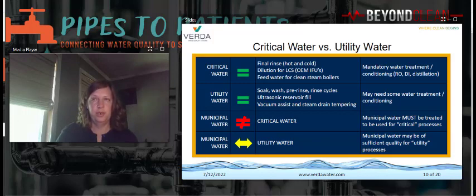Critical water must be treated and conditioned. Municipal supplied tap water isn't of sufficient quality for final washer disinfecting rinses or for pure dry steam for sterilizers. Utility water quality standards aren't as strict. Processes like basic soaking, washing, and rinse cycles use utility water. Also, utility water is used in the fill tanks in ultrasonic cleaners. Sterilizers use utility water, but only to temper steam drains and generate the Venturi effect for pre- and post-vacuum cycles.